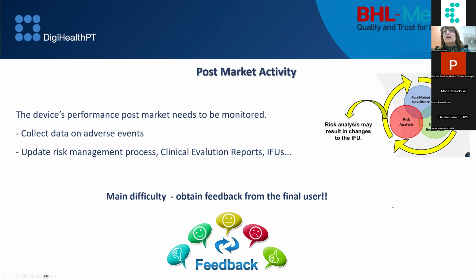Post-market activity was also another challenge that we faced, because we need to monitor the performance of the medical device after being on the market. And this is a snowball, because it's not just performing the post-market activity. We perform the post-market activity, and then we have to update the clinical evaluation, the risk analysis reports, the IFU, so everything is connected. And our main difficulty in this activity is to obtain the feedback from the final user, because BHL sells to distributors. Our end contact is the distributor, so it's not easy to obtain the feedback from the one who is using the device. So this has to be negotiated.